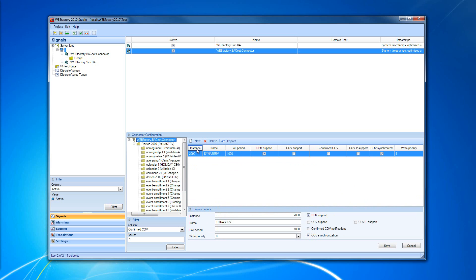The first property in this grid is the Instance, and any device must have this unique instance number. The Name is compulsory but doesn't have to be unique. The Poll Period is the period of time between interrogations. RPM Support means Read Property Multiple is supported when this checkbox is marked, allowing several property values to be read in a single RPM query. The Change of Values notification is supported if this checkbox is checked.